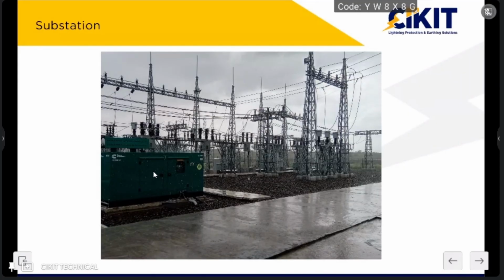So this is a sample image of a substation. Some of the commonly used equipment in a substation: the first component is the surge arresters or lightning arresters, which are placed before the transformer for protecting the equipment from surges. The second commonly available equipment are the transformers. Then for measuring purposes, we will be using CT and PT. Apart from that, for isolation, we will be using air break switches and isolators. Then we will be having circuit breakers. And for operating the circuit breaker, we will be using a lot of relays. Each and every substation will be having a lot of components, and all these components will be designed for handling this much higher rating of power.